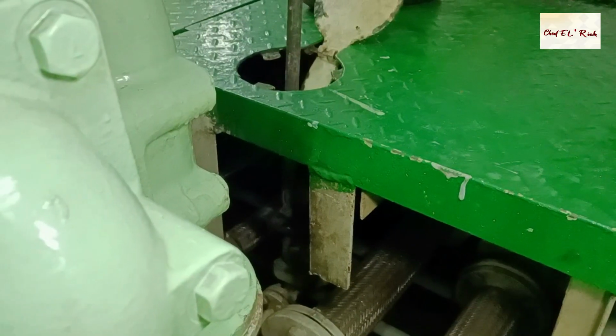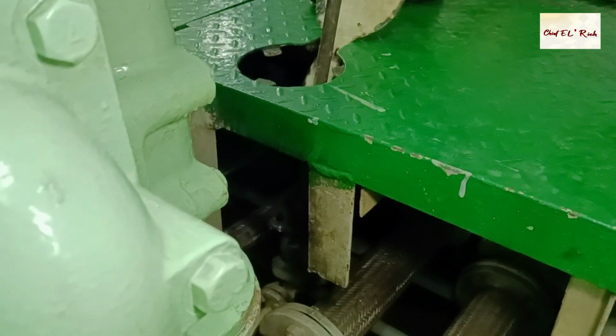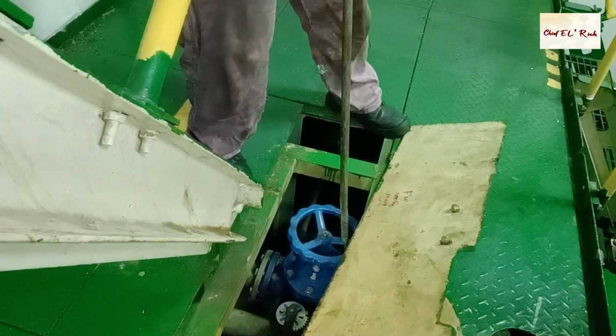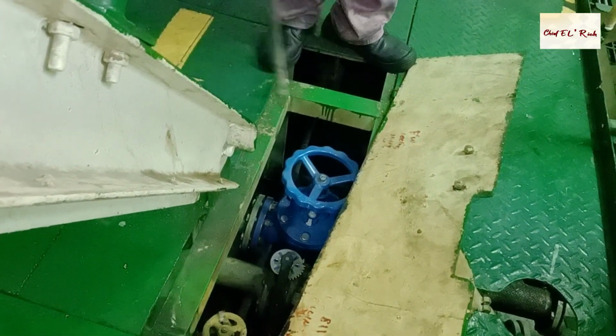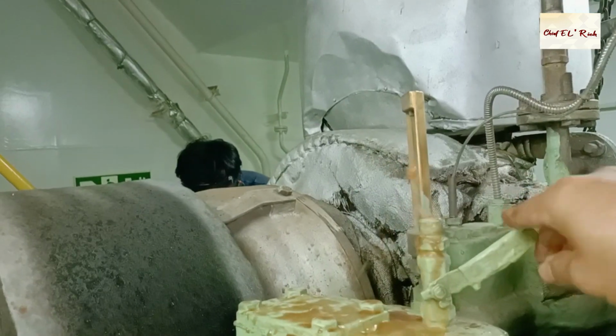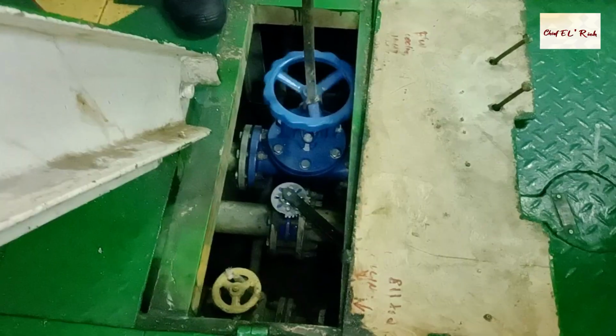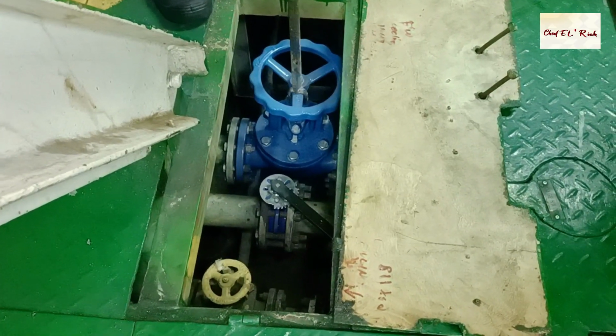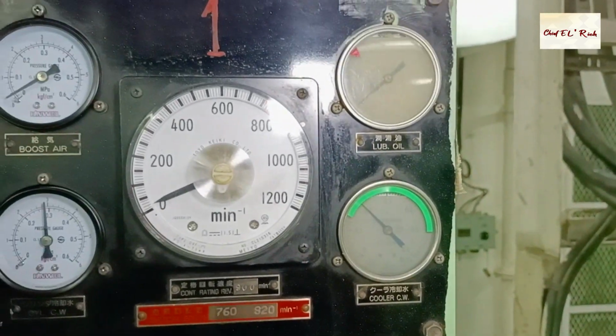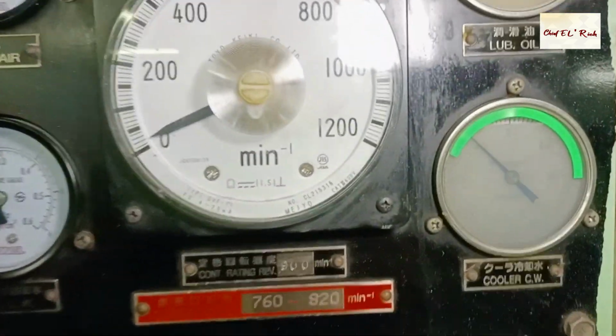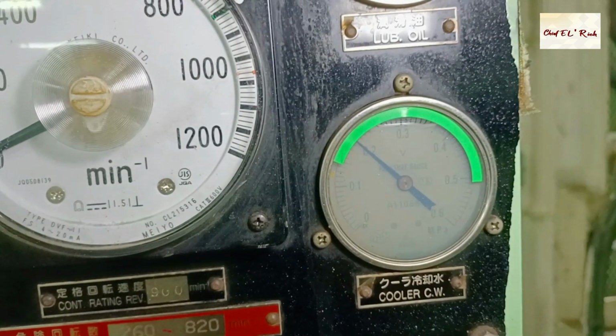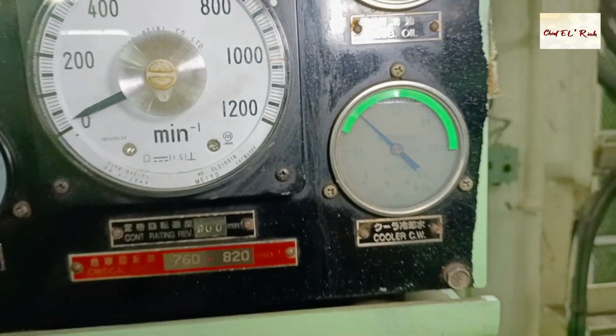Close the drain valve. Open the air vent valve. Open first the generator jacket circulation valve. Gradually open the inlet and outlet valve and open the air purge valve until the air is taken out from the system. Now fully open the inlet and outlet valve. Check the cooling water pressure in the gauge board manifold. Once the pressure is normal, we can now start the engine for testing.